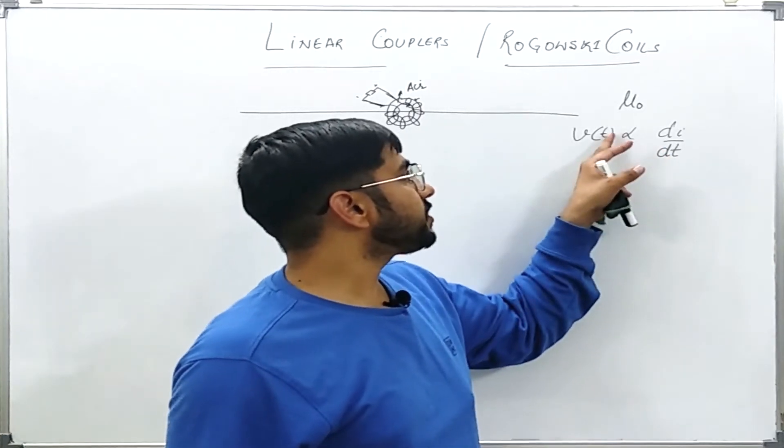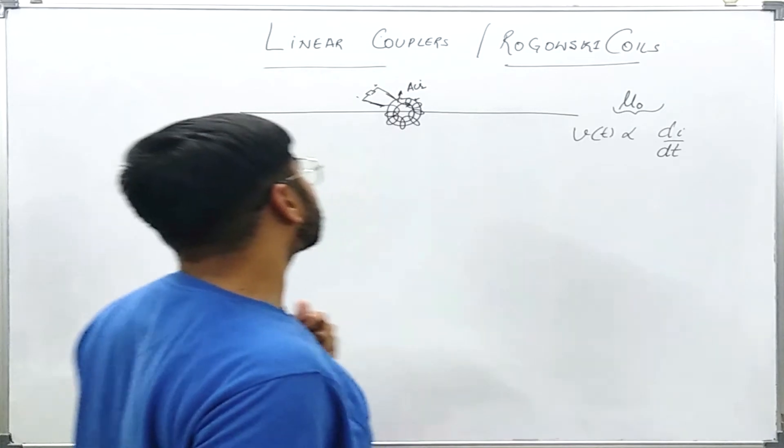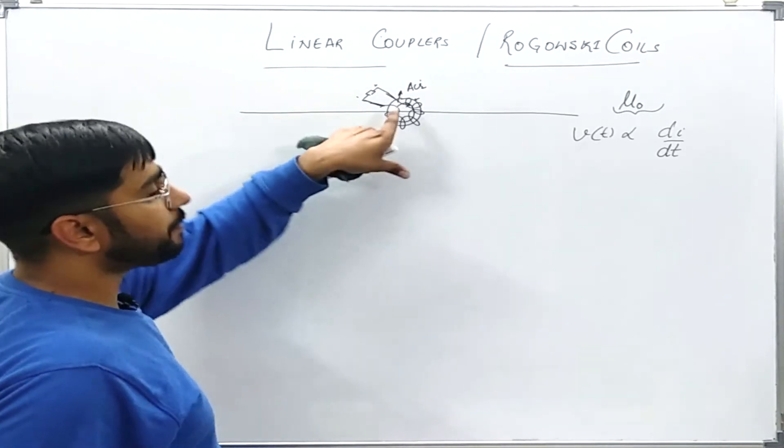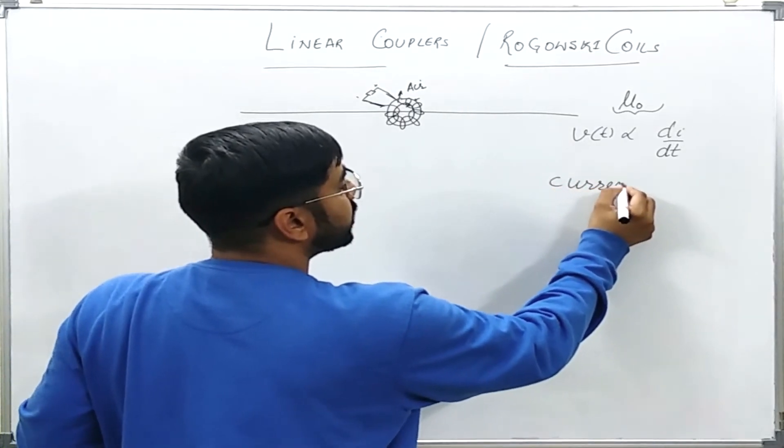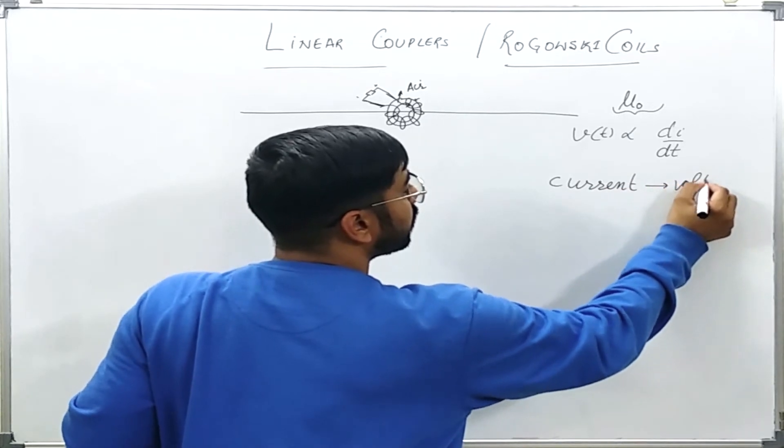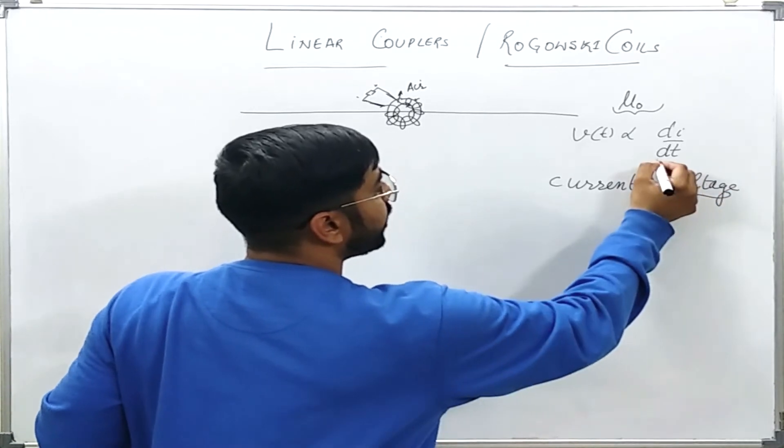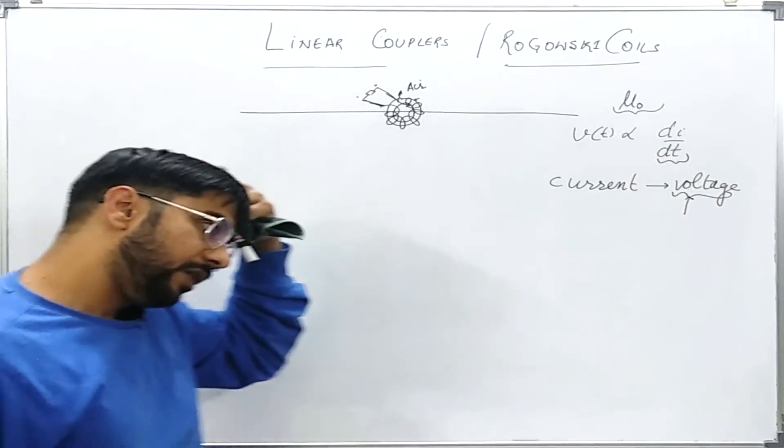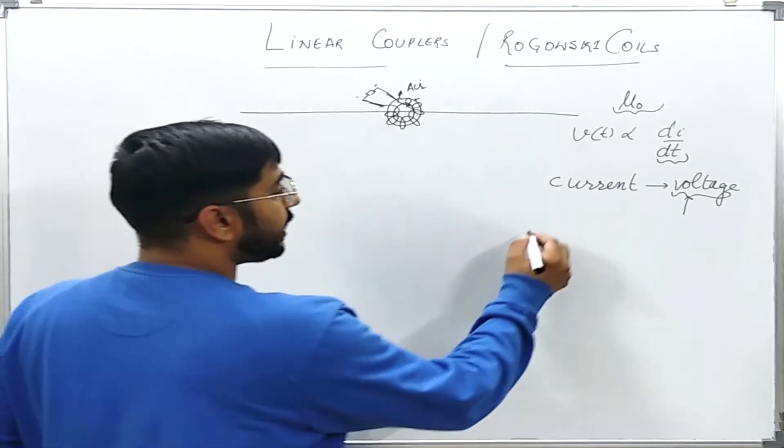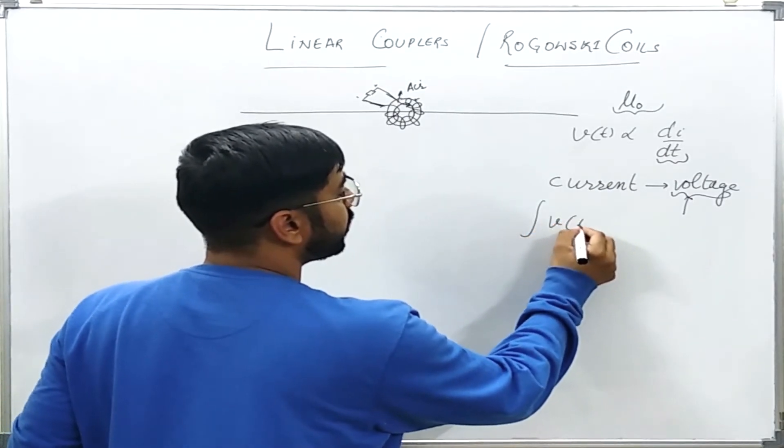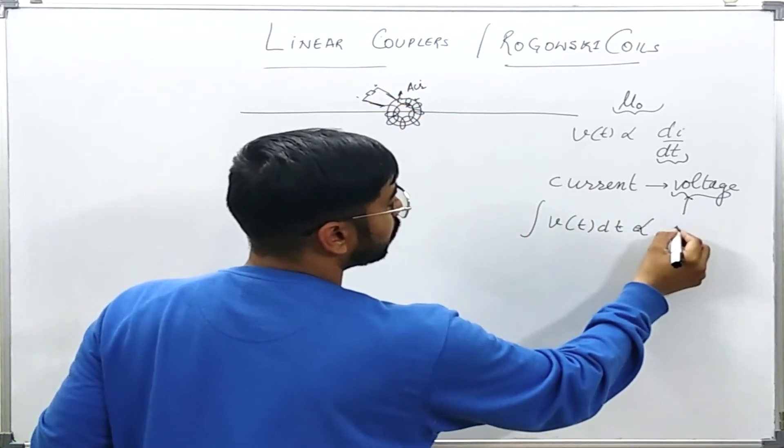This rate of change will be linear because of a fixed permeability. There is no saturation phenomena. This kind of linear couplers will work as kind of current to voltage source converters. This voltage will be linearly proportional to rate of change of the primary current. What we will do? To read the current directly we will put an integrator which will integrate the output of this coil. That thing will be proportional to i(t).